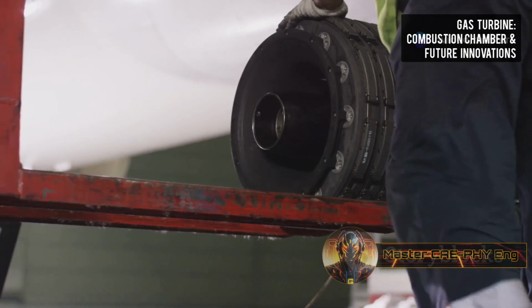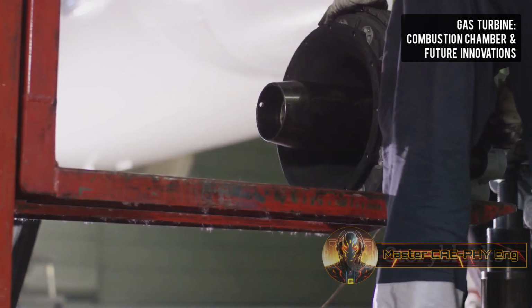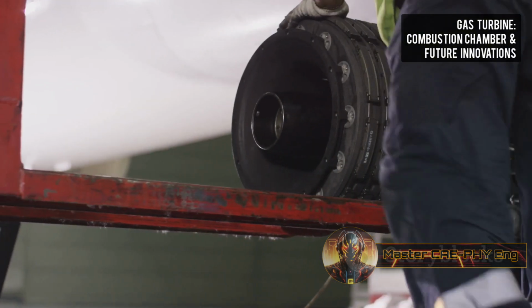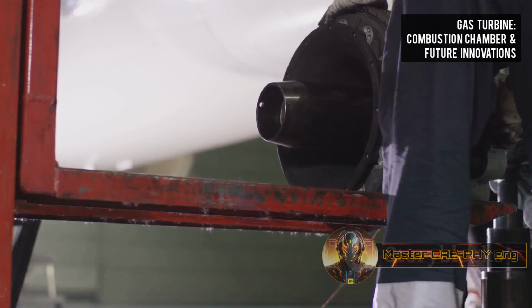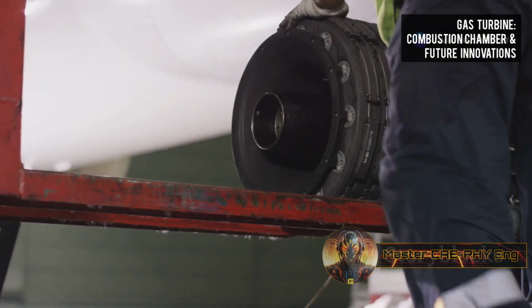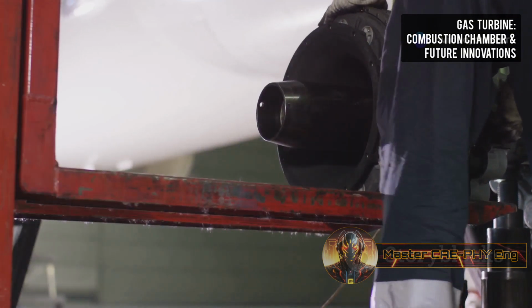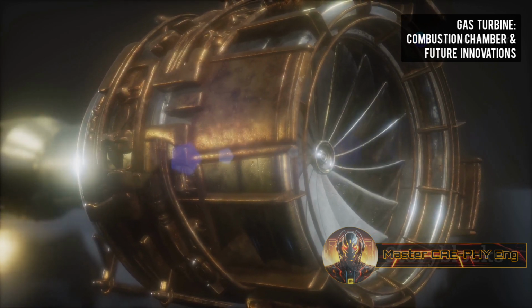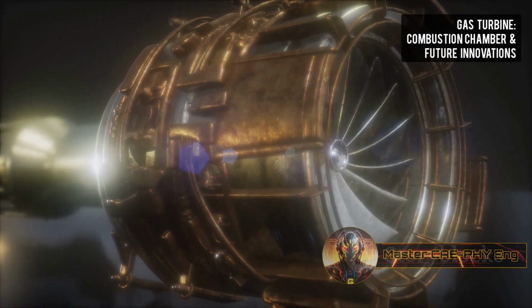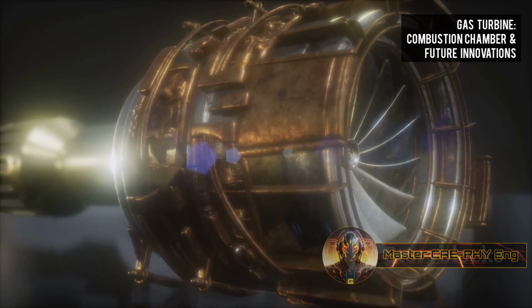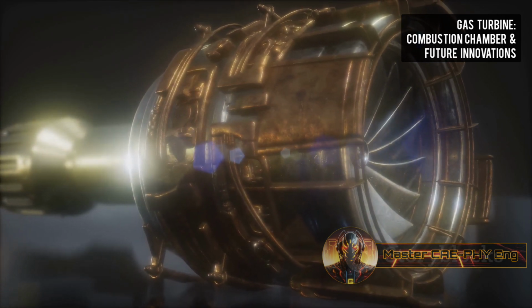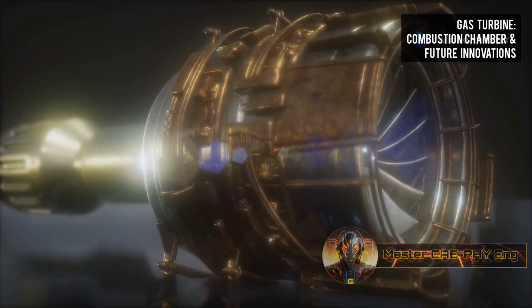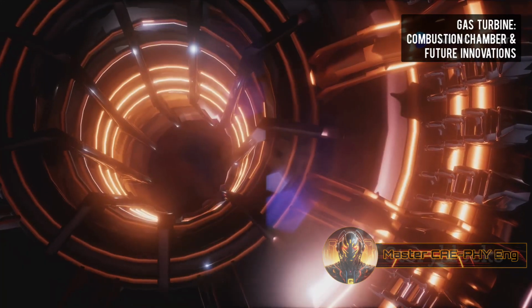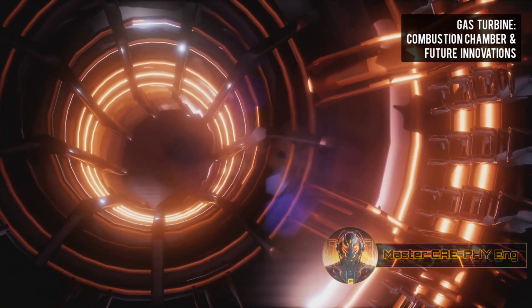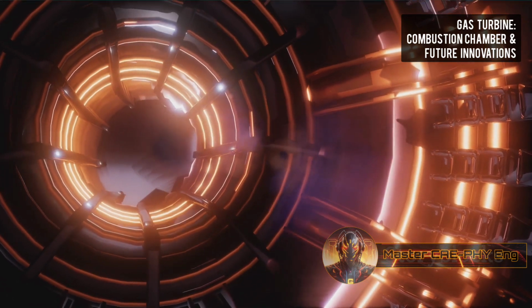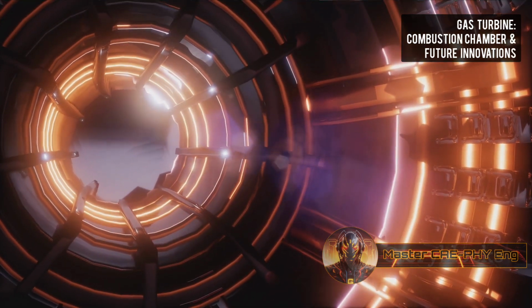The materials used for combustor liners, transition pieces, and fuel nozzles must possess high temperature strength, excellent oxidation and corrosion resistance, and good thermal fatigue properties. Nickel-based superalloys, such as Hastelloy X or Haynes 188, are commonly used for combustor liners due to their ability to retain strength at elevated temperatures and resist oxidation. For even higher temperature applications, ceramic matrix composites, or CMCs, are emerging as promising alternatives.